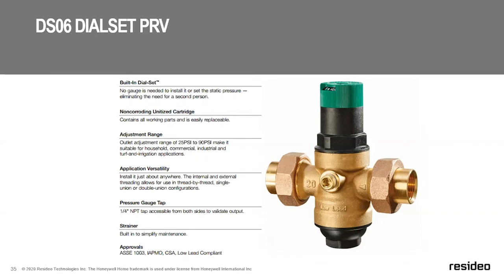What makes this PRV different? Well, first of all, we call it a dial set PRV. That right there is a really interesting thing that you don't see on other PRVs. That dial on the top has a number, and that number tells you very precisely the amount of pressure that you're setting it to, and then you put a little cap on it, and it's done. The nice thing about this is you don't need a gauge to check your pressure. If you want to, you can. You can see in the middle of the valve, there's a port where you can put a gauge on if you like, but it's so accurate that a gauge is not necessary to set your pressure.